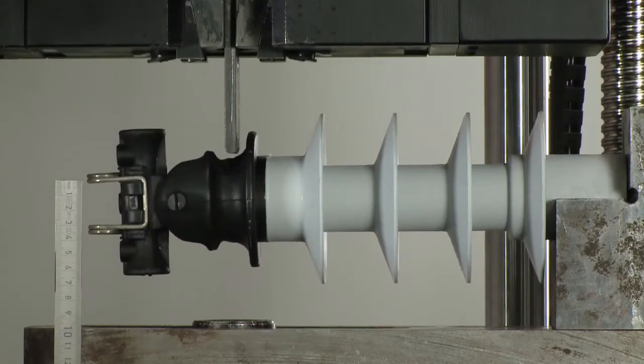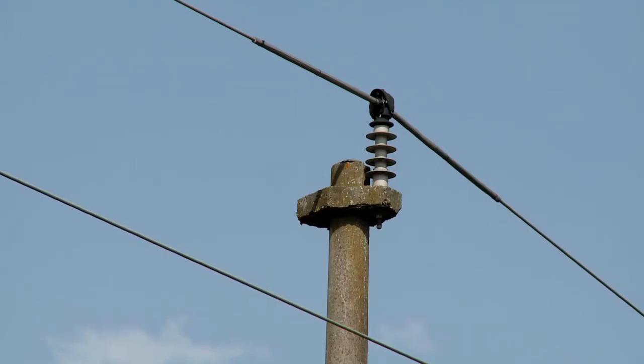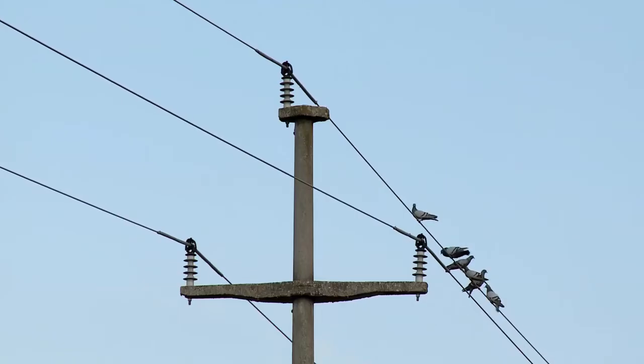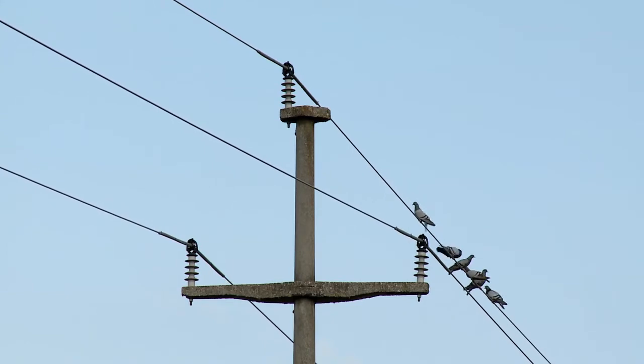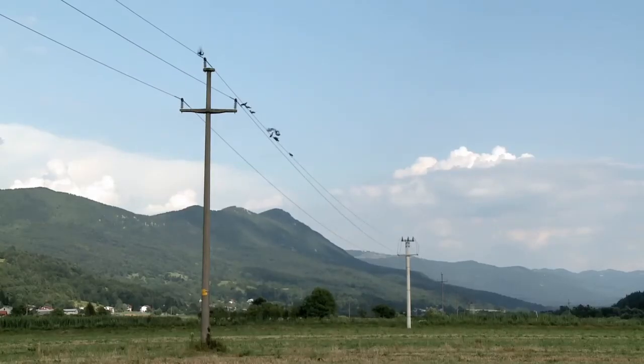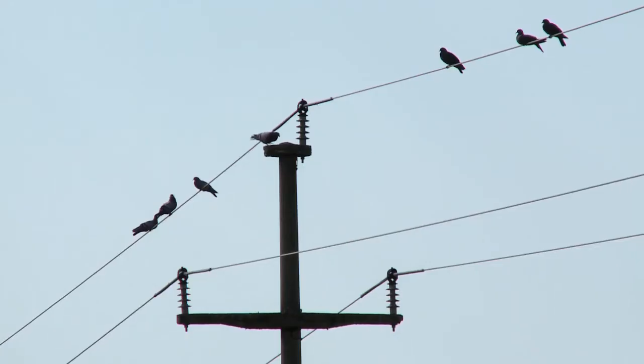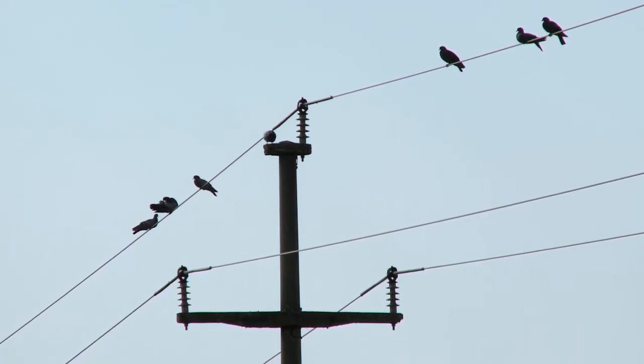An additional 1-meter-long silicone coating added onto the bare conductor at each side of the insulator is intended to completely secure the carrying poles and thus prevent short circuits. This solution also provides secure protection for birds.